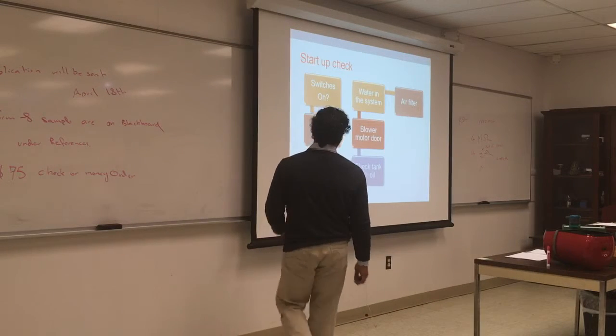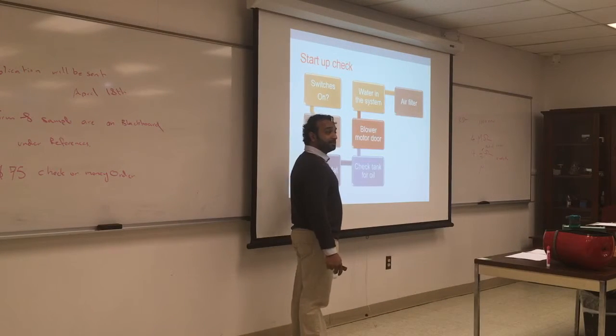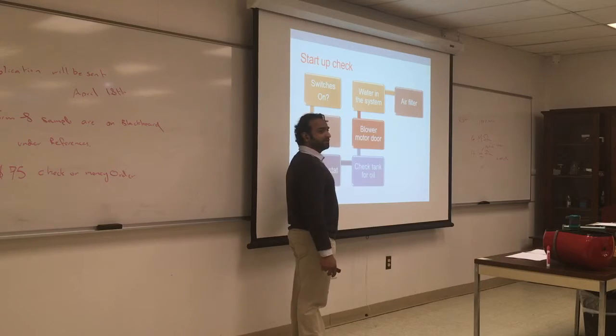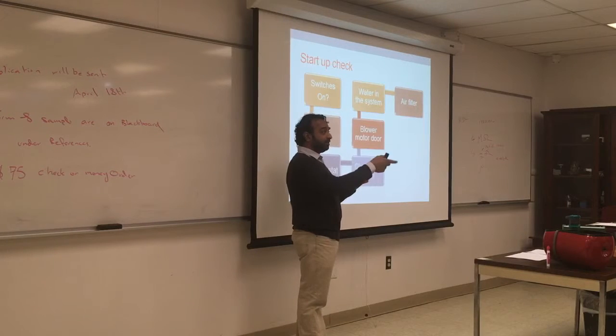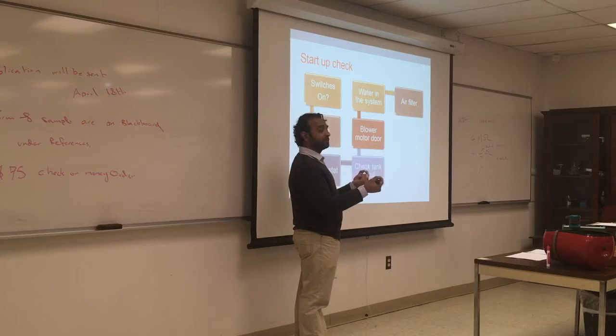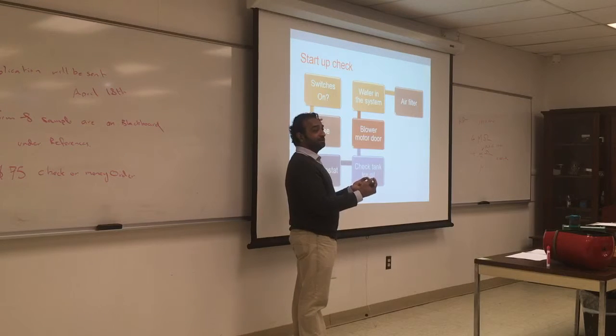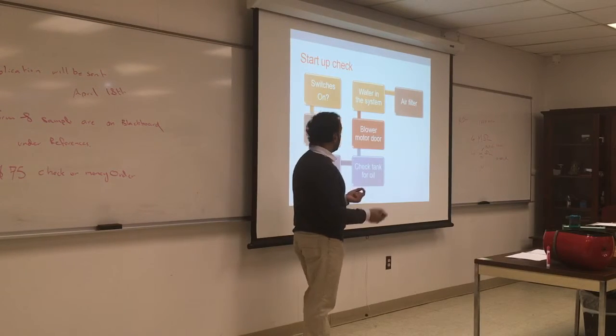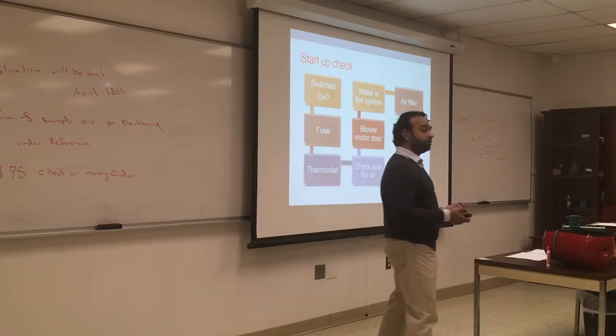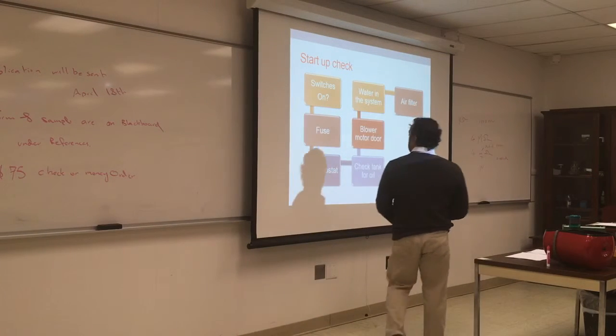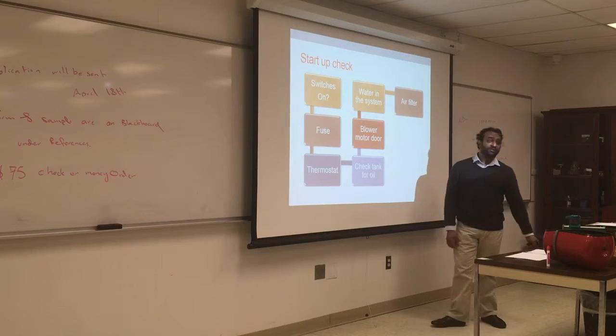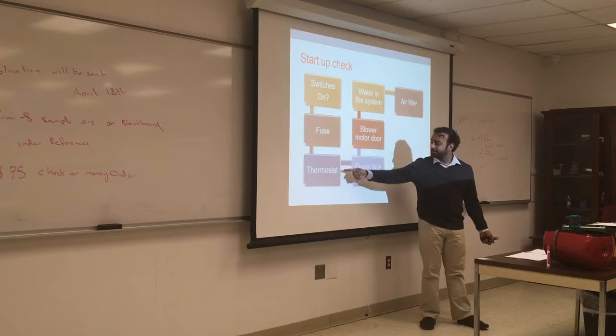Okay, so startup check. Switches are on. Check the fuse. Check the thermostat. How do you check the thermostat? You can do a continuity test. Turn it on high and do a continuity test. It should be continuous. That means the switch is made. Turn it off, and it should be discontinuous. That's the simple way to check the thermostat. Again, with the electronic thermostat, it gets more and more complicated. So, startup check: switch on, fuse, thermostat.